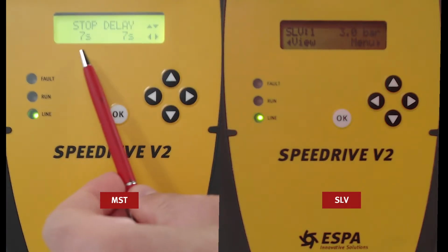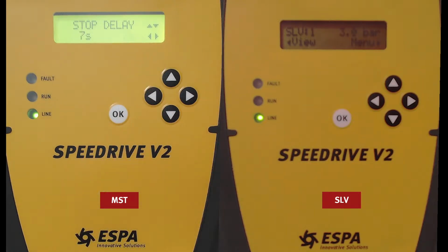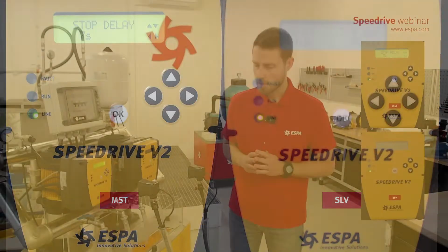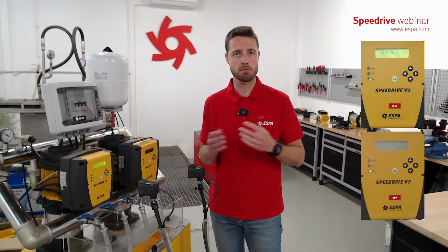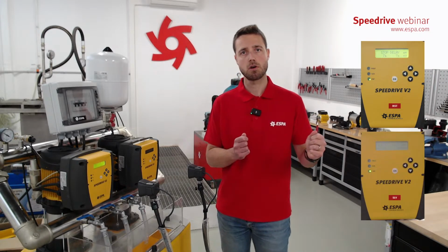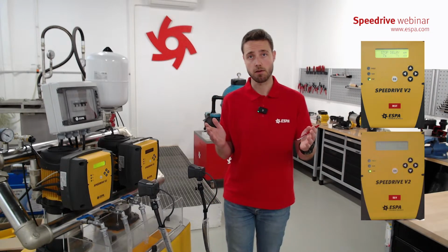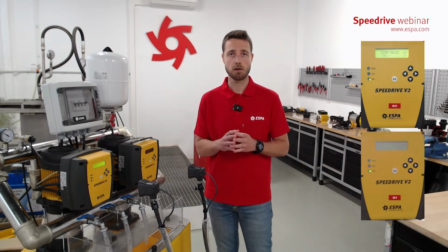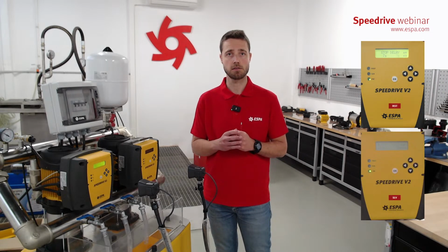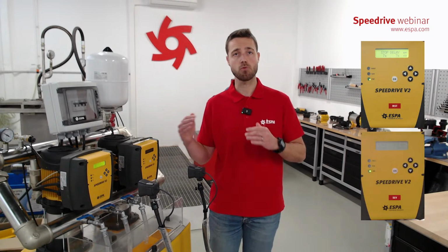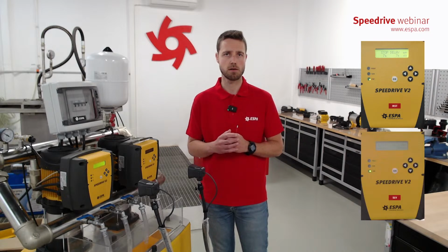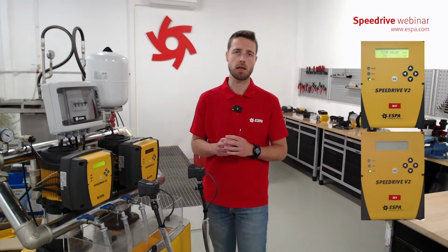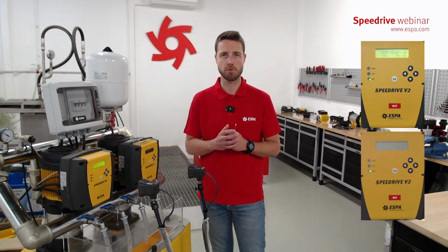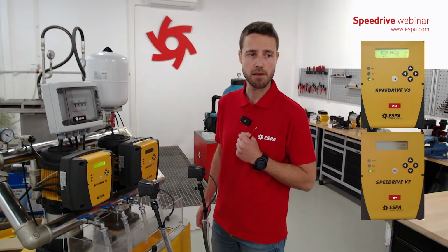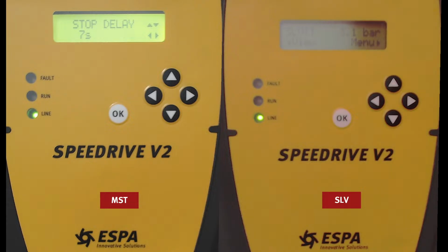Stop delay. When stopping the pump, we will have a delay of 7 seconds. So what's the meaning of that? Once we open many valves and we have a flow, and then we close all the valves, the pump will not stop immediately. We have no flow, but the pump will continue for 7 seconds in order to maintain the pressure in case we open another valve, so we don't have to be starting, stopping, start, stop the pump. So we will not stress the engines and the pumps, and we can extend the life of the pumps with this system. This is a setting that can be modified as well. Normally 7 seconds is the one that comes from our manufacturing plant. Let's continue.